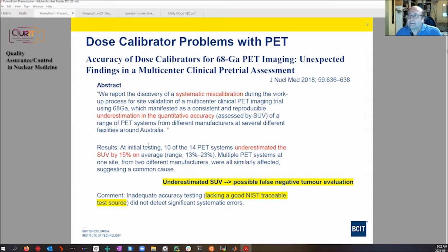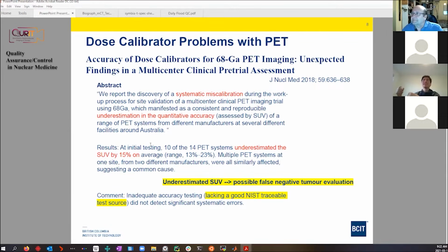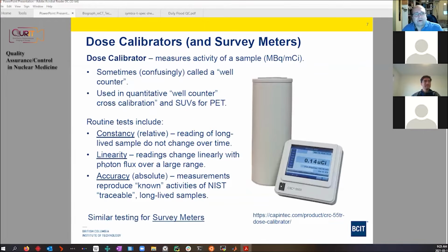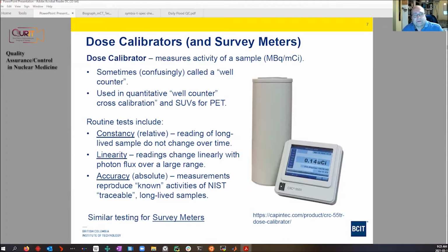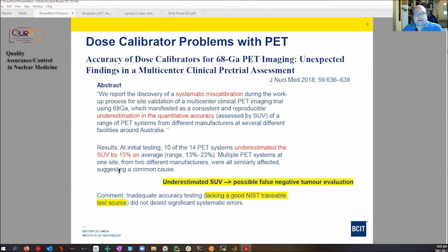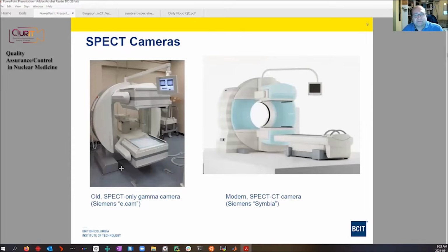So Barry, just to interrupt, I confirm we at the clinic are doing that accuracy check daily. We have those sources that Barry has been talking about, and every morning the technologists check and make sure that the activity corresponds to the activity that we're supposed to be measuring that day. So when you're doing constancy, you're using these tests. If you do the constancy, you put in a source and you do the setting for that radionuclide, you're essentially doing the accuracy at the same time. So that's a bit of a horror story of failed quality control.